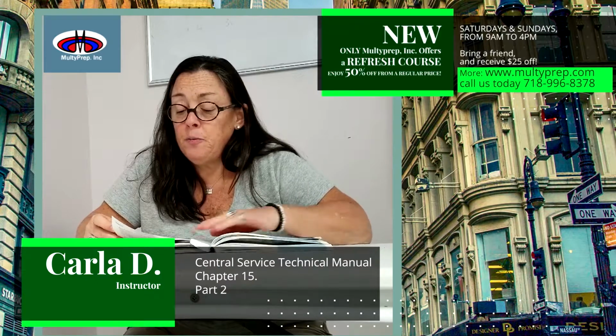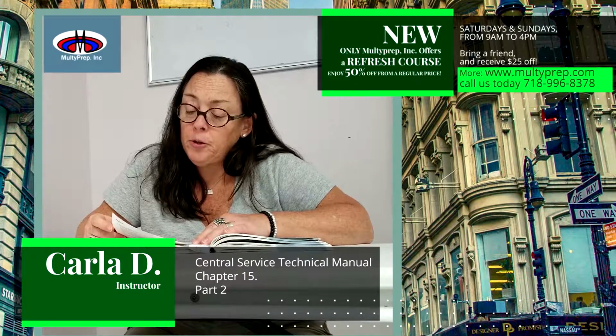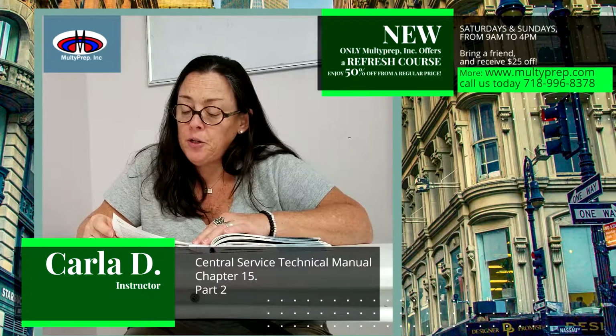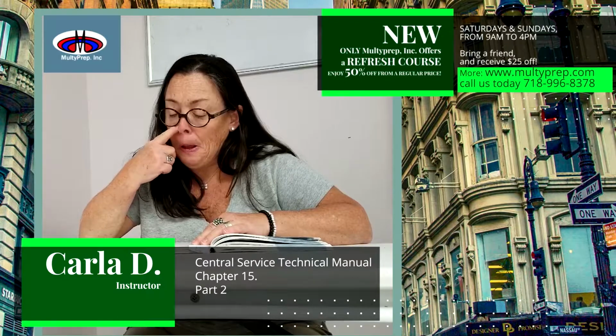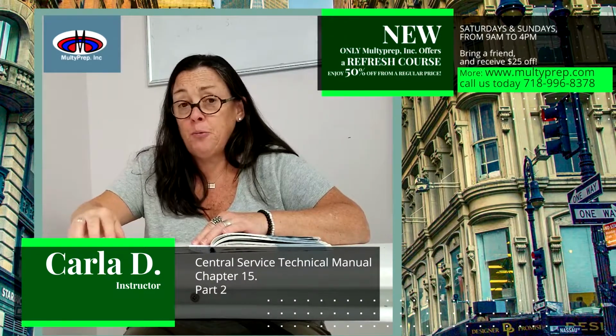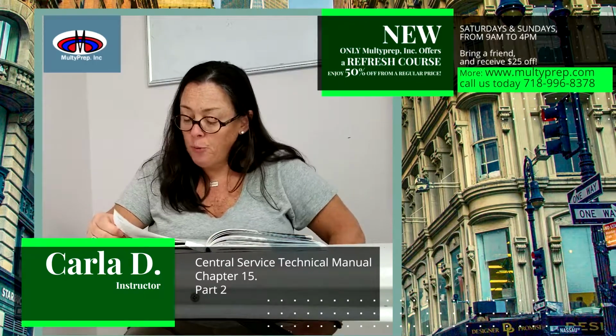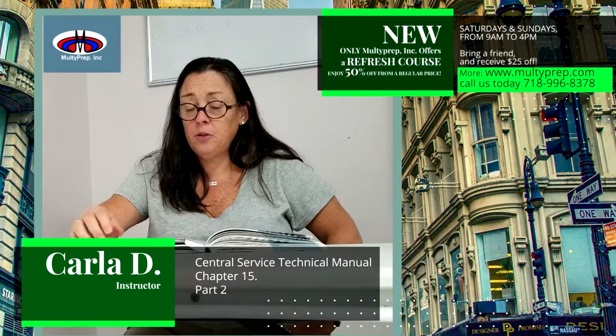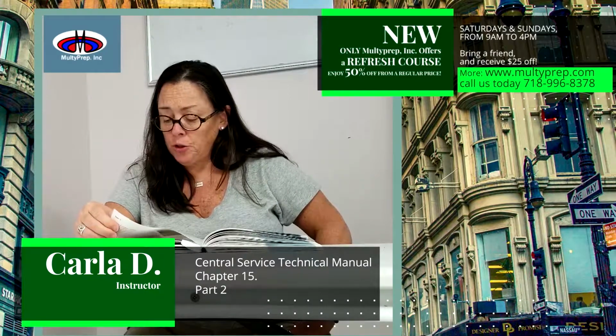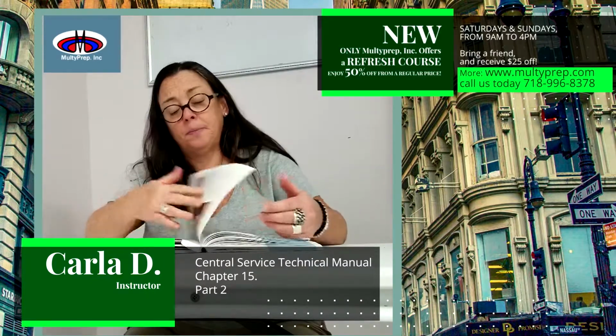Loading hydrogen peroxide gas plasma sterilizers. As with other low temperature sterilizers, hydrogen peroxide gas plasma sterilizers must be properly loaded for effective sterilization. If the available amount of hydrogen peroxide is reduced because it reacts or is absorbed before reaching all surfaces, a sterilization failure could occur. Therefore, the chamber should not be overloaded. See figure 15.2. Excess moisture remaining on devices can cause the cycle to abort. Consult the manufacturer's instructions for use for suggested drying methods.